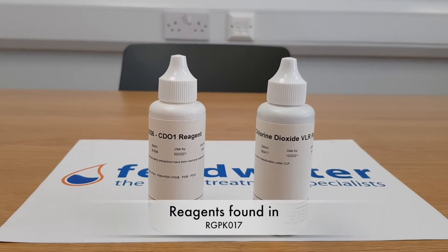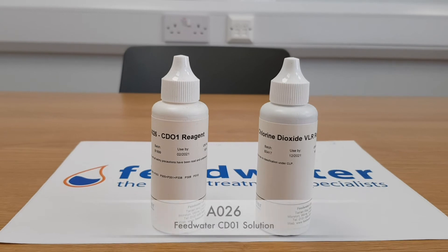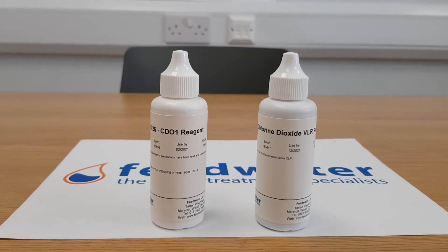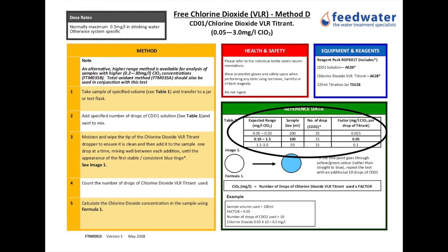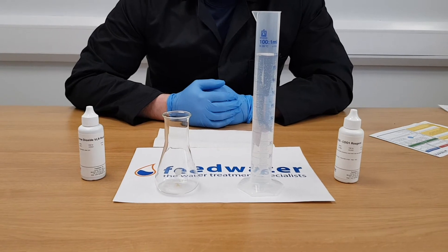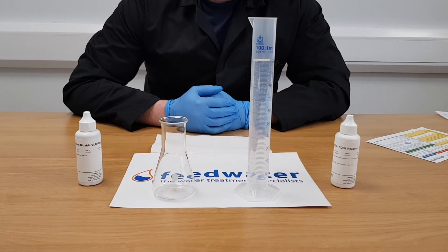For this test you will need the following reagents: Feedwater CDO1 solution and Feedwater chlorine dioxide VLR titrant. For most applications we expect the range to be 0.1 to 1.5 mg per litre of free chlorine dioxide, so we would recommend using a 100 ml sample volume. If you're expecting higher or lower results than this you may wish to opt for an alternative sample volume as shown. In this example we'll be using a 100 ml sample volume.